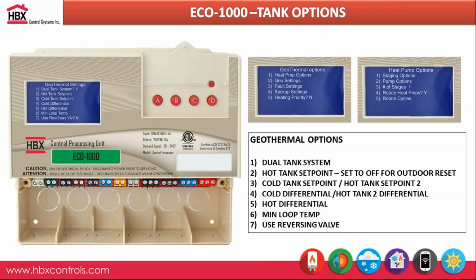So in terms of how you want to use the 1000 in terms of your tank options, you can have it tell the controller that you're using a single buffer tank for heating or cooling, or you can just tell the controller that we're doing a dual tank. Once you do a dual tank, it automatically changes the system interface to display a hot and cold tank on there. So if you see a hot and cold tank, that means you've set it up for a dual system option on the 1000.